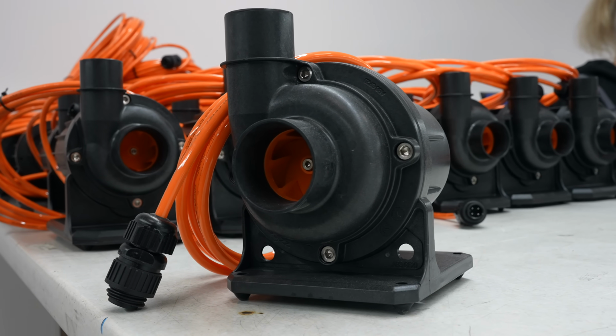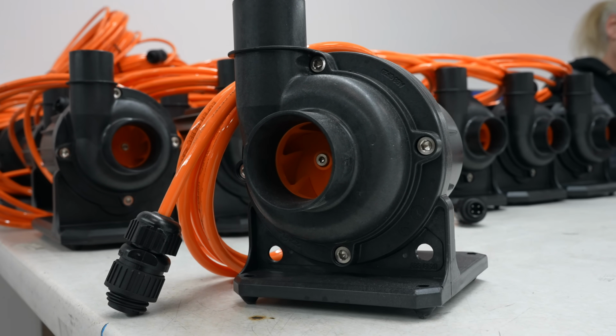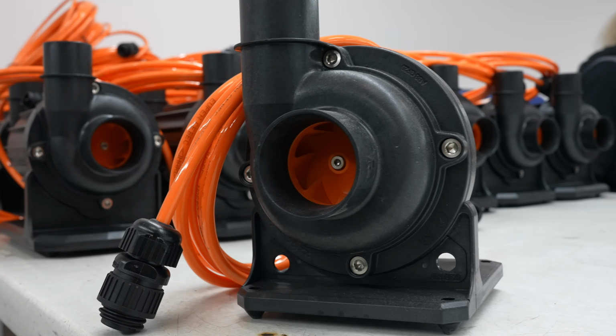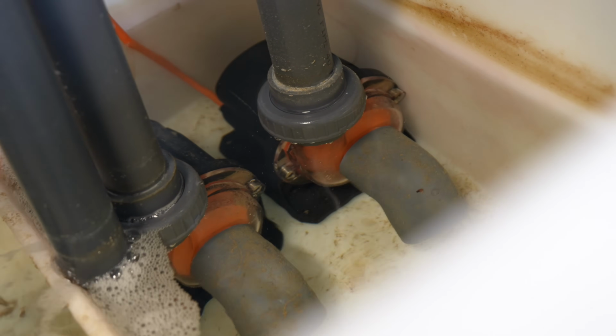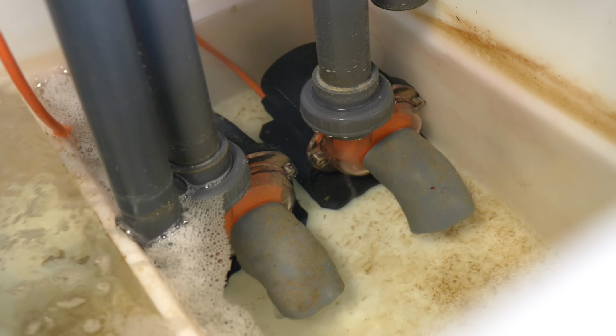I see the pumps being plumbed in wrong, and that doesn't necessarily mean there's a bunch of angles and valves and whatever in front, but there's also the pipe diameter. So just recently when I was in Baltimore, the National Aquarium in Maryland, I saw one of the few A200s that were actually plumbed in quite correctly, so with a 63mm or 2.5 inch on the intake and then 2 inch, 50 millimeters, out on the outlet of the pump. And that looks very weird on an A200, but it's actually the right size diameter.